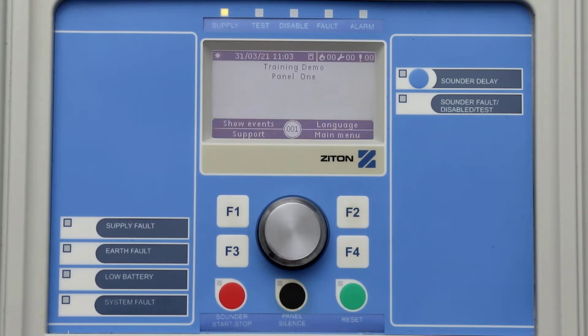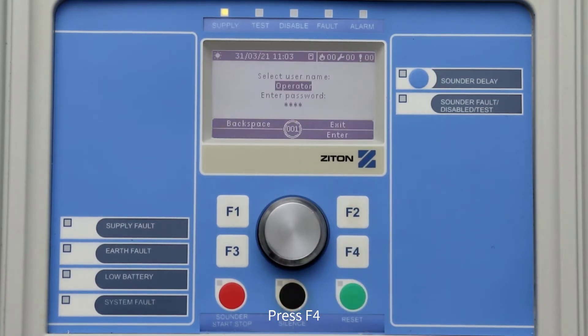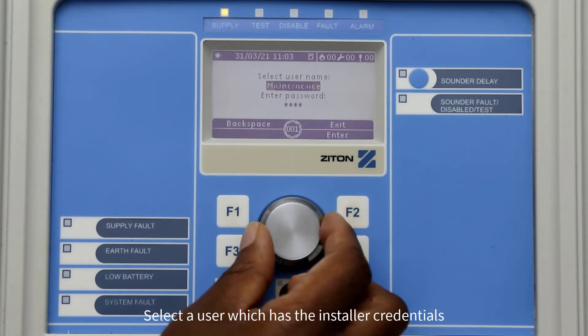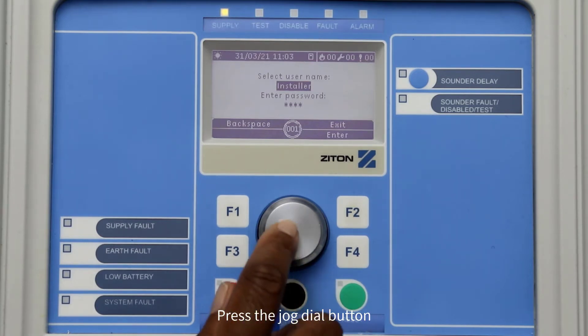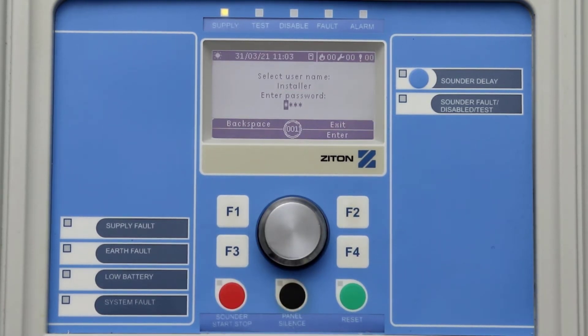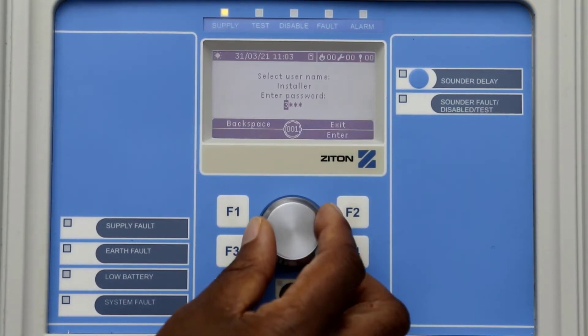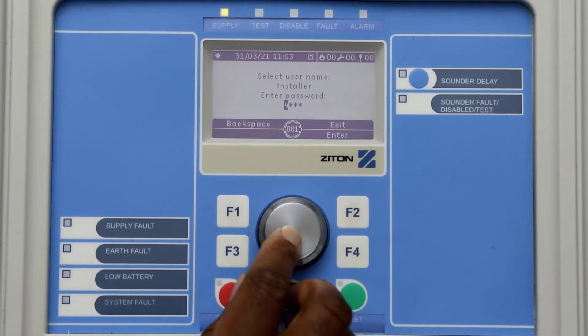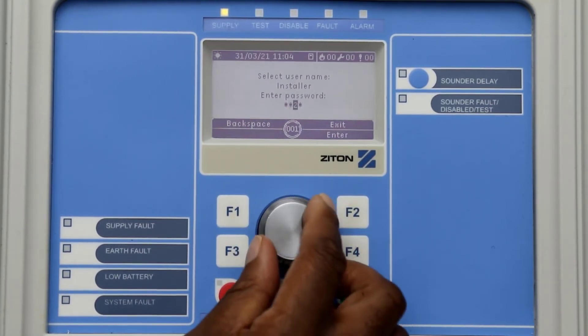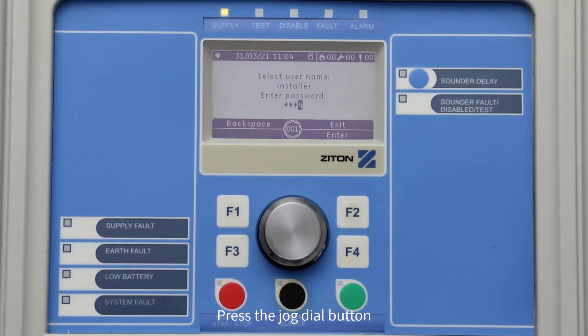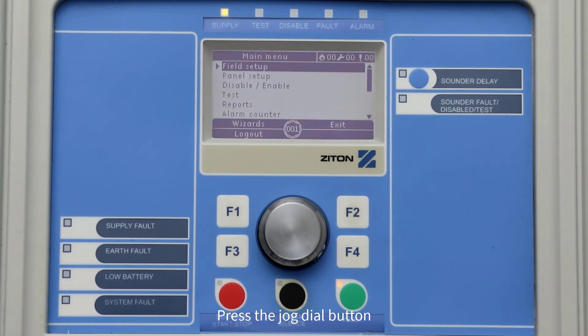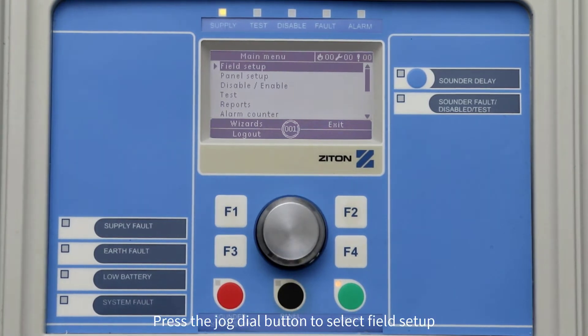To log into the panel as an installer, press F4 to select the main menu. Using the jog dial button, turn the dial and select a user which has the installer credentials, then press the jog dial button to scroll down to the password option. Select the correct password by turning the jog dial to select each digit, pressing the jog dial button to move the cursor to the next digit. Then press the jog dial button or F4 to enter into the installer menu.